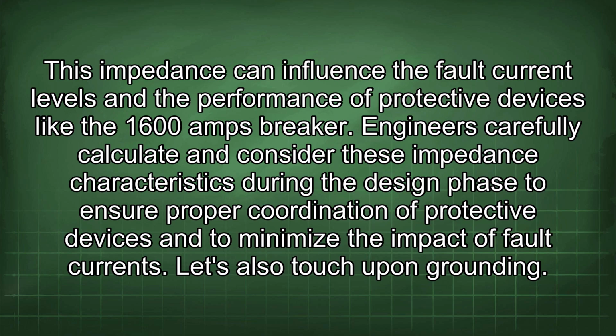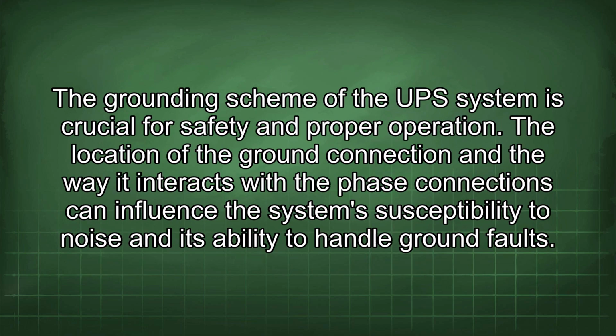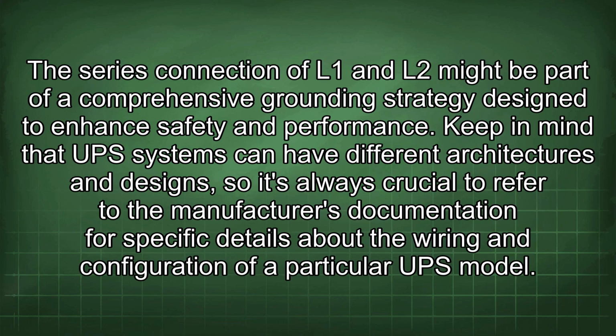Let's also touch upon grounding. The grounding scheme of the UPS system is crucial for safety and proper operation. The location of the ground connection and the way it interacts with the phase connections can influence the system's susceptibility to noise and its ability to handle ground faults. The series connection of L1 and L2 might be part of a comprehensive grounding strategy designed to enhance safety and performance.